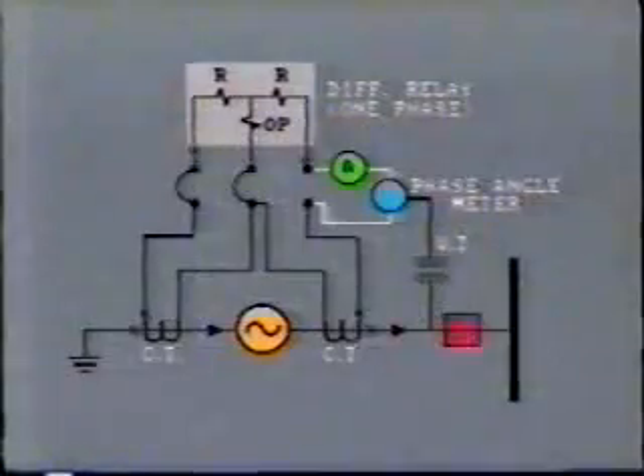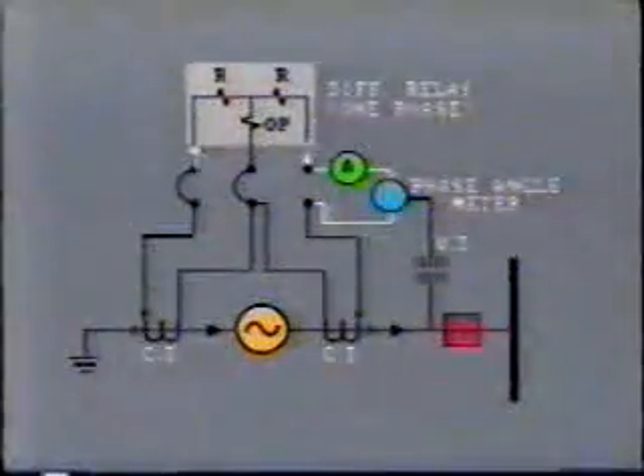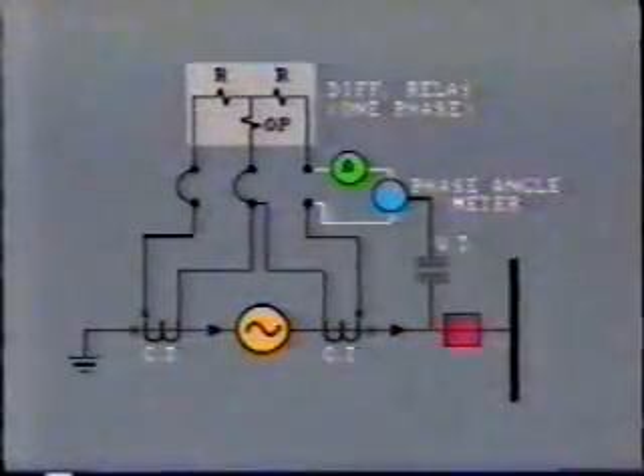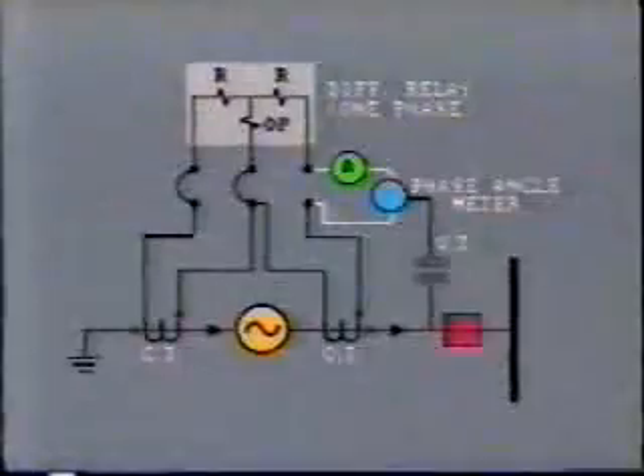The current enters at one relay terminal and exits from the other. This is correct if there is no internal fault. If the test shows different phase angle relationships, then the CTs have been incorrectly connected. However, this problem should have been discovered earlier by secondary or primary injection tests.